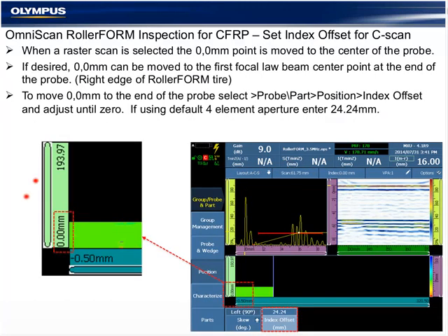We're going to fine-tune our C-scan a little bit for the index offset of the probe. When we selected raster scan from the scan inspection type, the software automatically moves the 0, 0 position on the probe to the center of the probe. This is a feature that's used in immersion tanks that makes rapid scanning with overlap extremely convenient and fast.